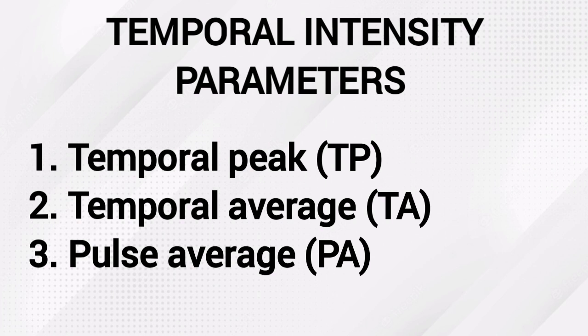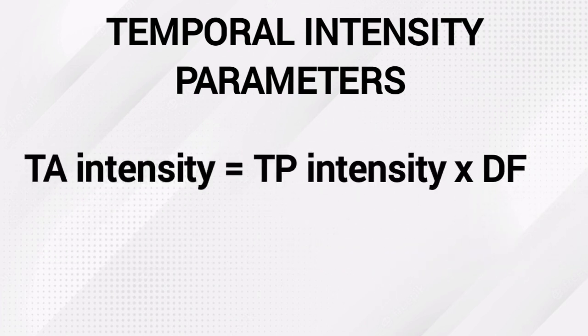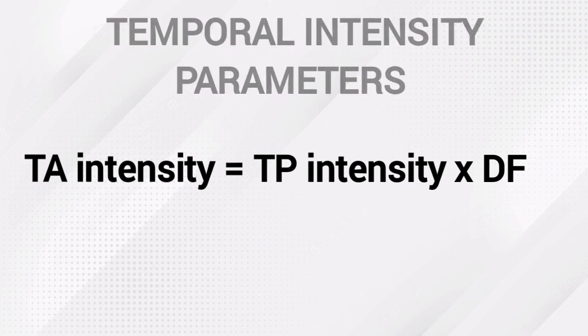Now, TA intensity is the temporal intensity averaged over both the pulse duration, that is the on time, and the receiving time, the off time. Now, since the system remains off for a much longer time than it's on during each cycle, the TA, temporal average intensity, is relatively low, because TA intensity is related to the TP intensity by the duty factor, and the equation for that is TA intensity equals TP intensity times duty factor.